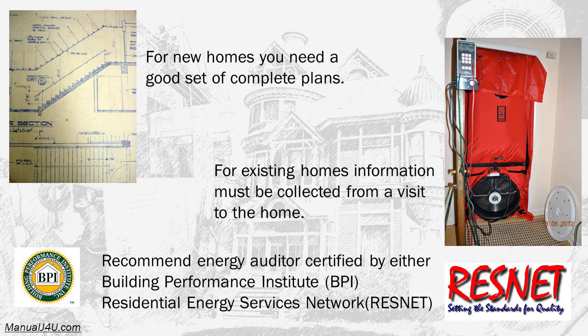For new homes, Manual J can be performed from a good set of drawings. For existing homes, the house needs to be surveyed and measured. Information on dimensions, building materials, and the effects of age must be obtained. A blower door test for evaluating air infiltration is an absolute must.